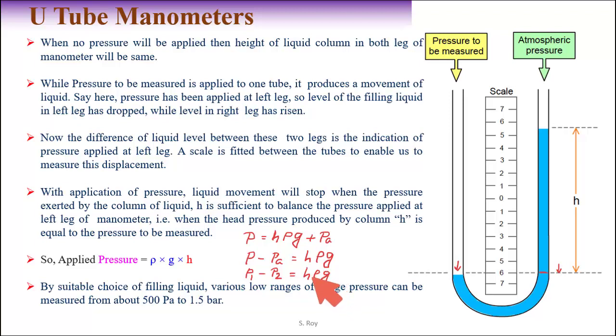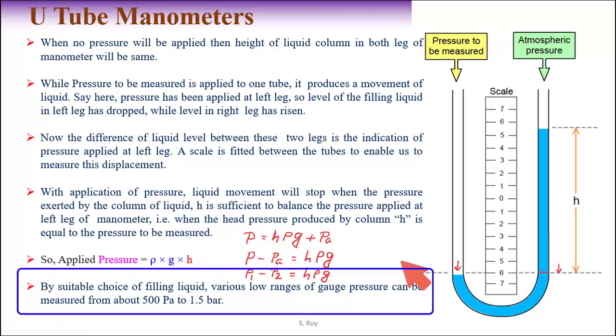Here rho is the density of the liquid used inside the manometer. Mercury is a suitable liquid normally used. By suitable choice of filling liquid, various low-range gauge pressures can be measured, with a range of approximately 500 Pascal to 1.5 bar. This is how the U-tube manometer works.